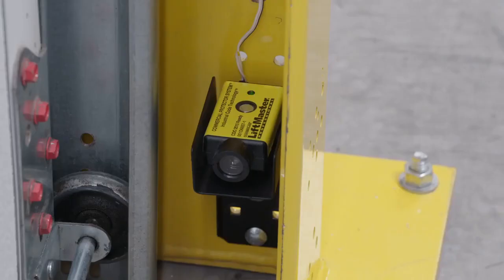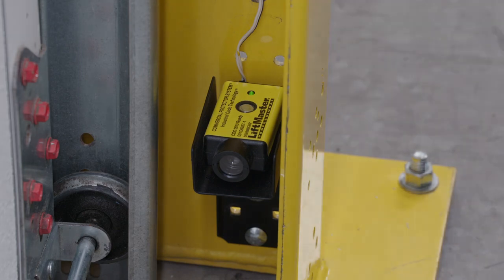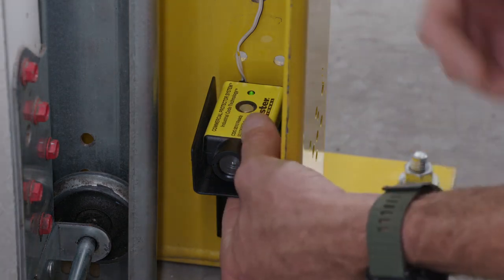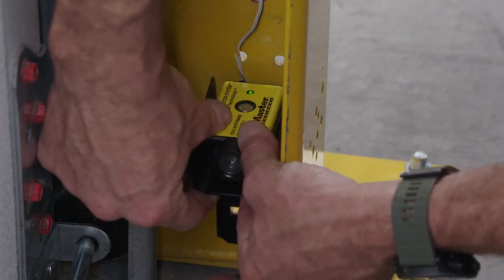After the Quick Start setup is complete, the operator automatically learns which monitored entrapment devices are connected. The lights on the CPSU sensors will be lit. This is your opportunity to align the devices. Look at the transmitter and receiver. The green light on each should glow solid. If either or both lights are blinking, adjust the position of the devices until the lights glow solid.